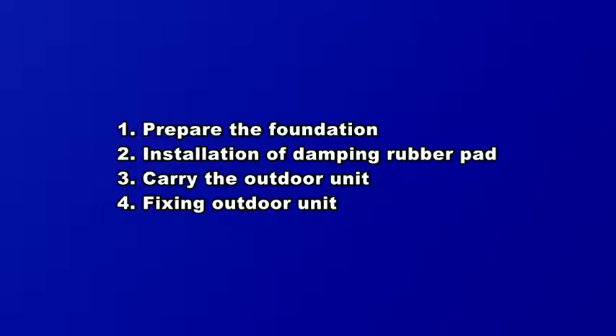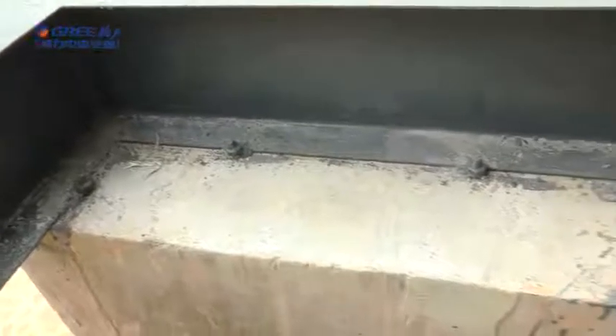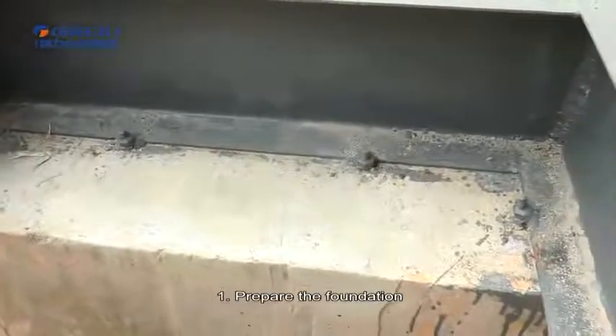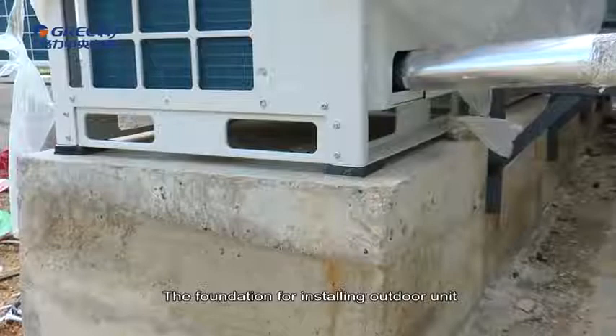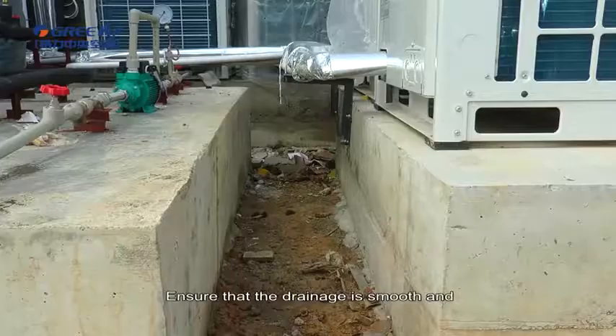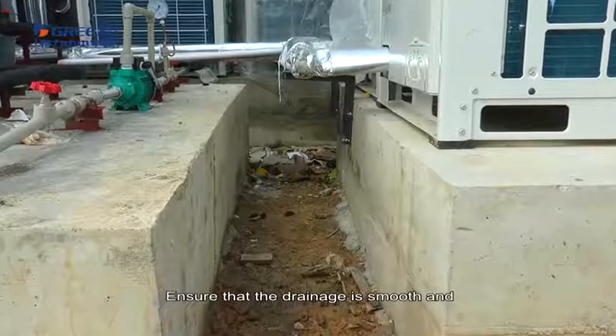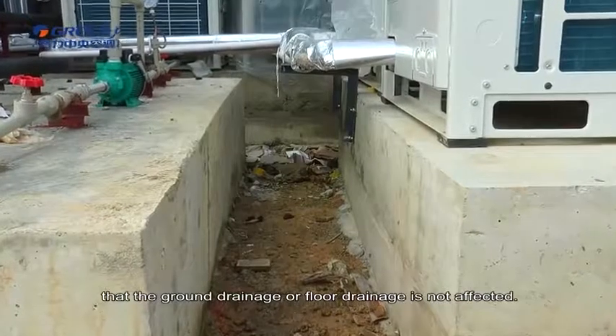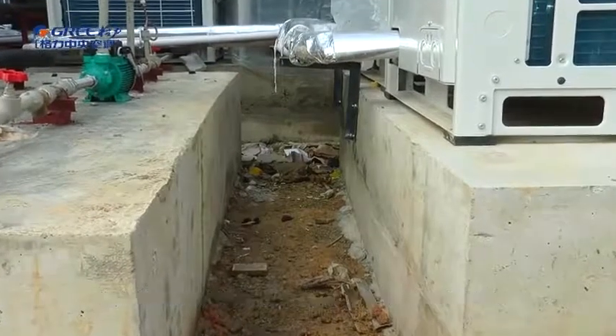Installation of outdoor unit. Steps to install outdoor unit. First, prepare the foundation. Second, installation of damping rubber pad. Third, carry the outdoor unit. Fourth, fixing outdoor unit. First, prepare the foundation. The foundation for installing outdoor unit must be strong enough. Ensure that the drainage is smooth and that the ground drainage or floor drainage is not affected.